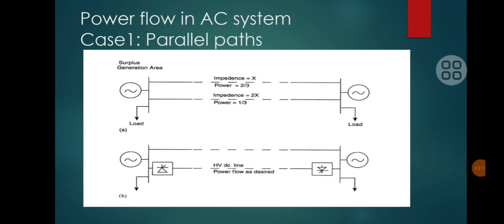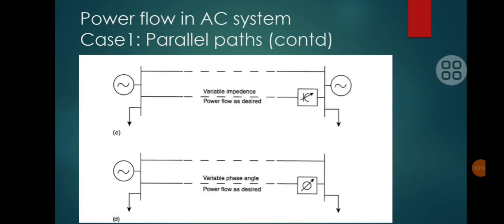The second case, figure B, shows a line with HVDC transmission. In such a case, electronic control of power is possible because of rectifier and inverter circuits. So, we can have better control and we can make the HVDC line carry power closer to its thermal capacity. Figures C and D show two systems with FACTS controllers. Figure C shows a series capacitor in the second line, and figure D shows a phase angle regulator in the second line. So, wherever these regulators are placed, power flow control is possible.